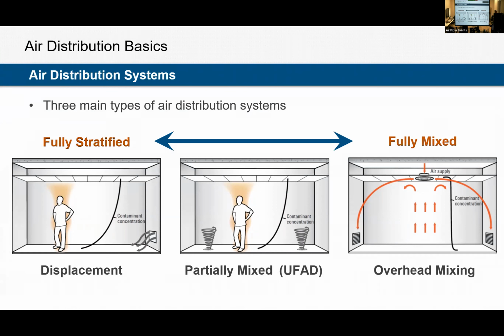Typically, we're going to have supply air coming from overhead, with returns either low in the space or back on the ceiling. The whole goal of a mixed system is to get the supply air to mix in the space. So we're discharging out of the diffuser, entraining the room air and getting the space to mix. I've got a couple of smoke videos where we'll really see that in action.